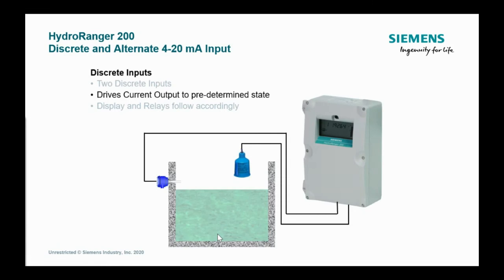There's something else that's called backup level override, or BLO. And what BLO allows you to do is to put in a point level switch. Typically, this is going to be a high-high or a low-low switch. And what you can say is if that point-level switch is ever activated, you can then drive the current output of the instrument to whatever value you define. So you could say if your transducer fails and it gets to trigger that high-high point, it can send 21 or 22.5 milliamps to the output, or 20 milliamps if that's what you define, and it will do that.